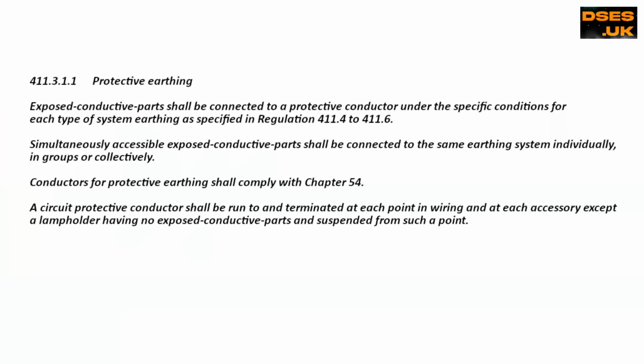That's just on an existing installation, of course. If this situation were something new that I'd just installed, Regulation 411.3.1.1 would apply. It states exposed conductive parts will be connected to a protective conductor that itself runs back to the earthing system in use, so I can't use the prior regulation to get around my own bad workmanship. Although of course that would never be needed, because I'm an electrical installation hero.